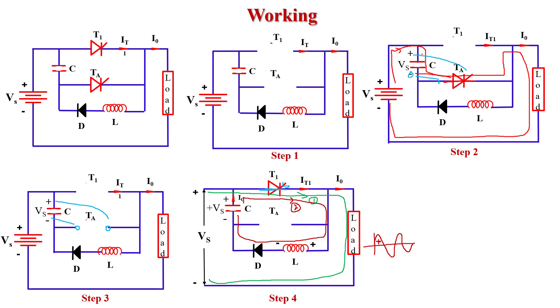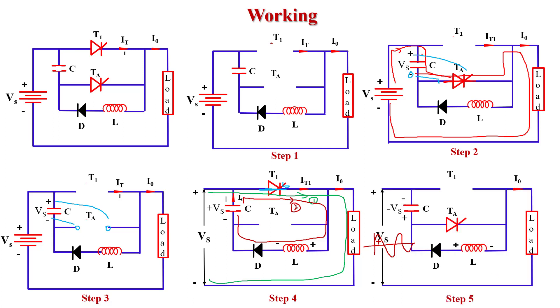After that, the inductor releases its energy and changes polarity — the left plate becomes positive and the right plate negative. The inductor releases its energy through the diode and capacitor, and the capacitor is charged again with minus Vs voltage. So here the capacitor initially charged with plus Vs voltage, and when current flows through loop 2, the capacitor charges with minus Vs voltage. The polarity is now upper plate negative and lower plate positive. This polarity of the capacitor will turn off the main thyristor T1.